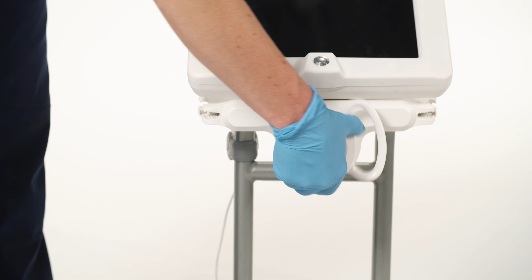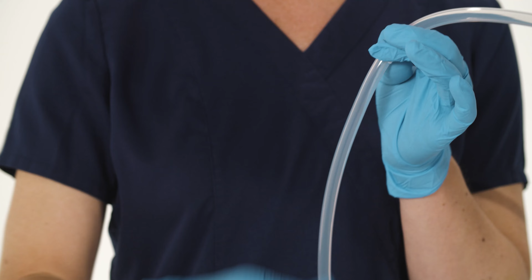The Sensica ring is a single patient use device that will provide continuous operation for 29 days. Each disposable ring is packaged with 1 positioning strip, which is used to create a band around the tubing. This band marks the segment of tubing to be inserted into the tube holder. This is necessary for the system to begin monitoring.